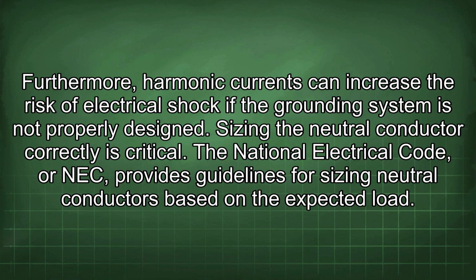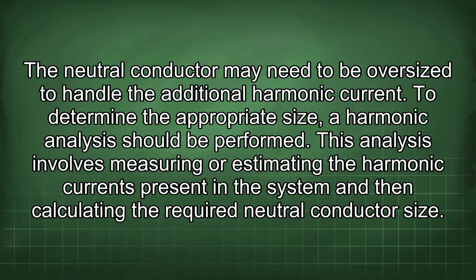The National Electrical Code, or NEC, provides guidelines for sizing neutral conductors based on the expected load. However, in applications with significant harmonic content, the standard sizing methods may not be adequate. The NEC Article 310 addresses neutral conductors. The neutral conductor may need to be oversized to handle the additional harmonic current. To determine the appropriate size, a harmonic analysis should be performed.